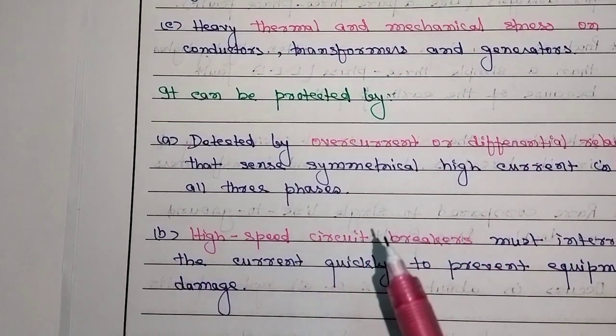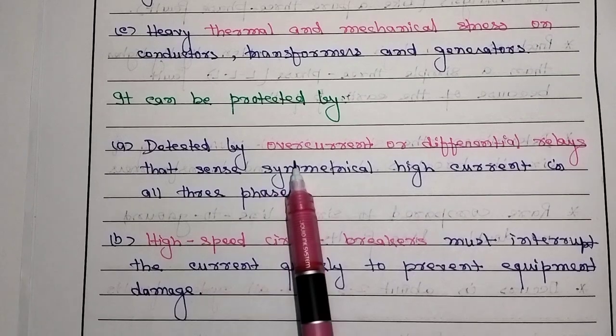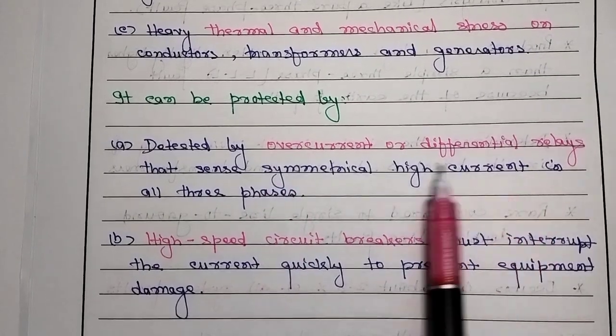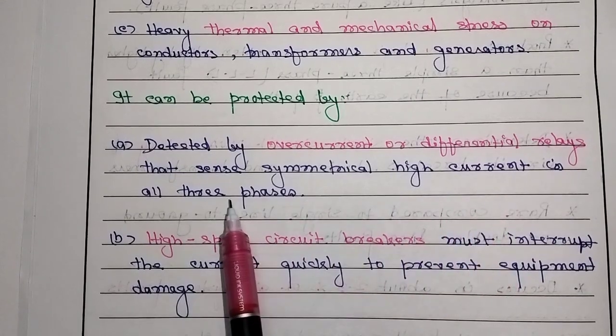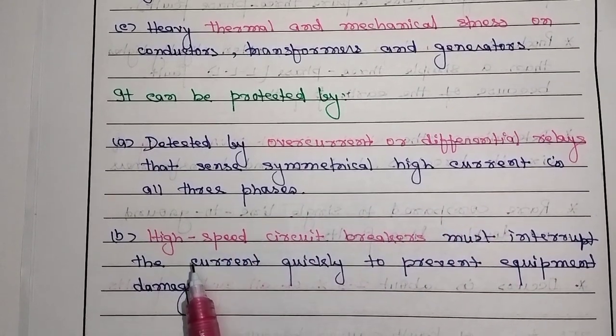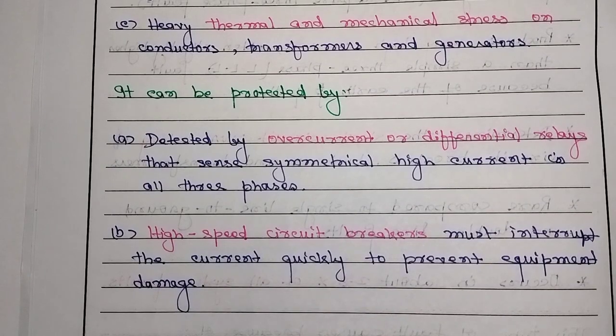Next, how can it be protected? It can be detected by the overcurrent or the differential relays that sense the symmetrical high current in the three phases. The last point is that a high speed circuit breaker must interrupt the circuit quickly to prevent equipment damage. So these all are the in-depth discussion regarding the faults. This is the entire story from the definition through types, features, causes, effects and protective measures, and the link with the short circuit capacity, presented in a single continuous explanation suitable for a lecture.